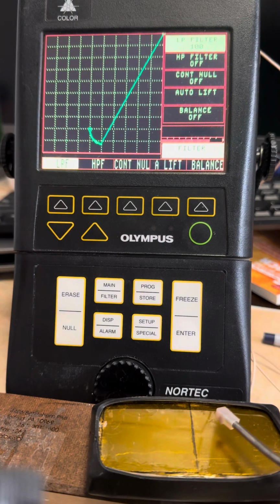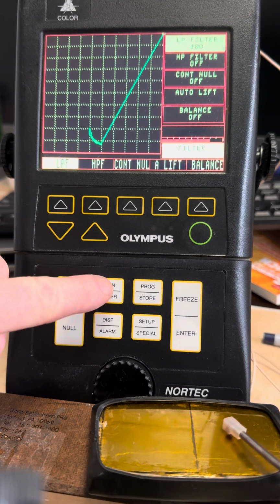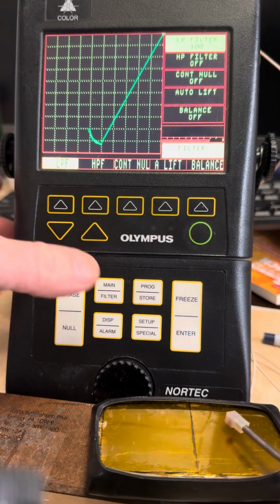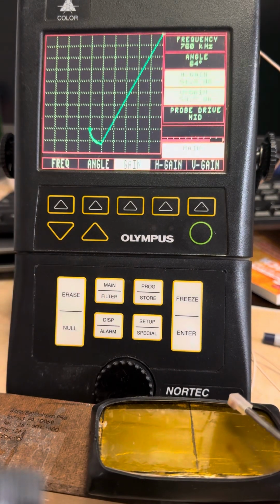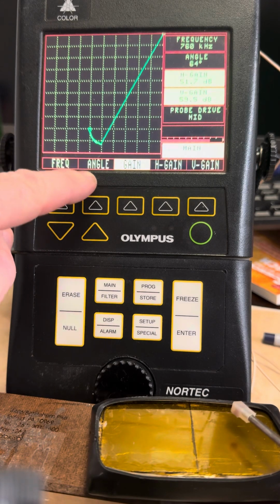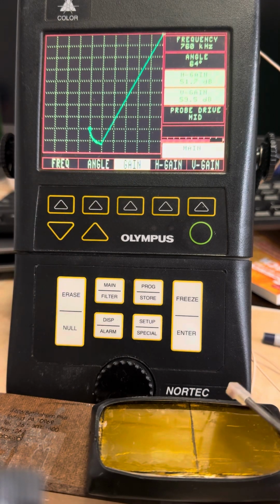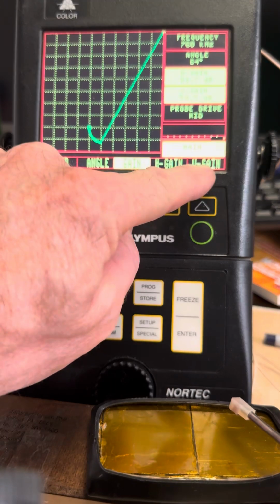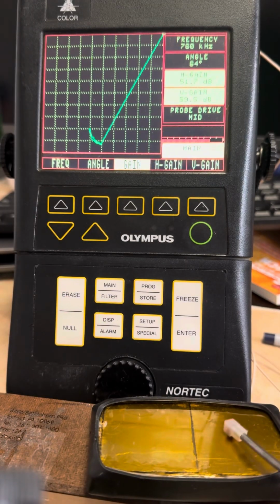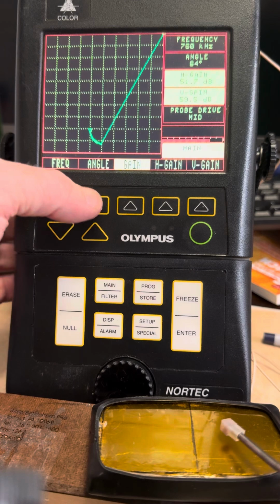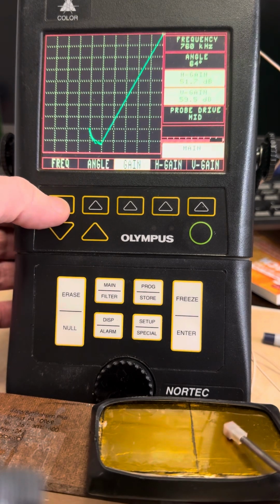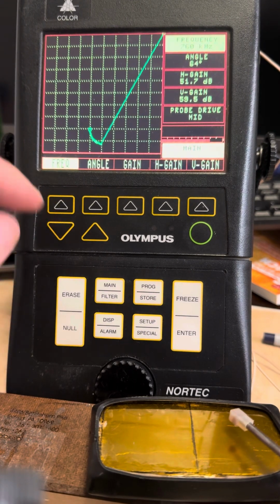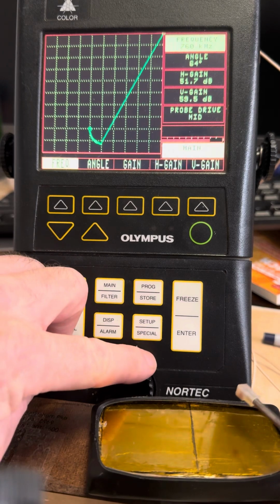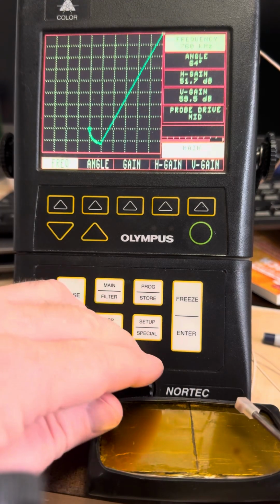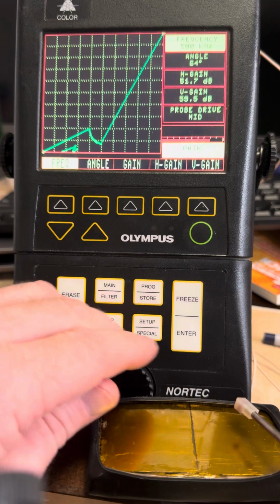So right now, to adjust the frequency and the rotation, we need to go to the main menu. So this button says main right here. We're going to select that once. Now you get frequency, angle, gain, and then you have your individual horizontal gain and vertical gain. So I'm just going to tap it. First thing I want to do is take the frequency, and we're going to adjust that first. So using the smart knob, if you look up here, that's the frequency. I'm just going to go to 300 kilohertz.